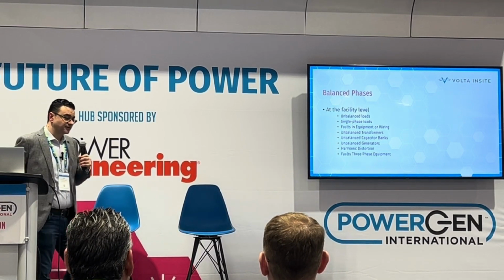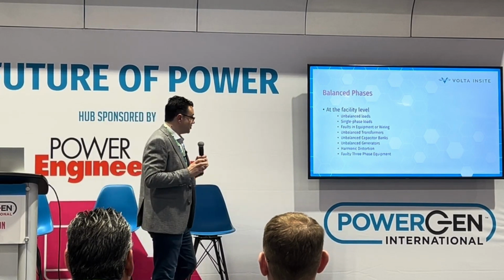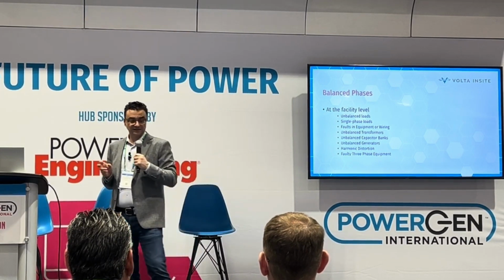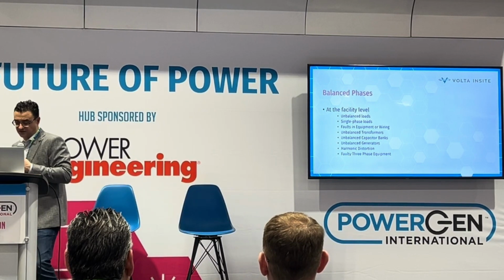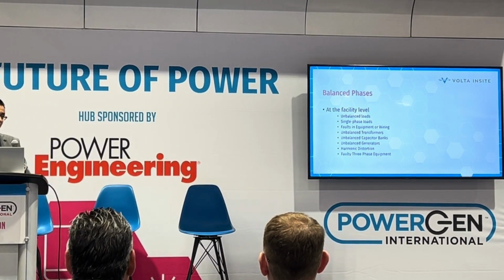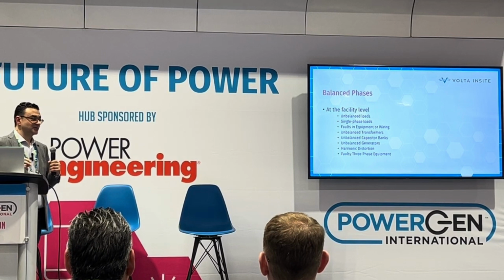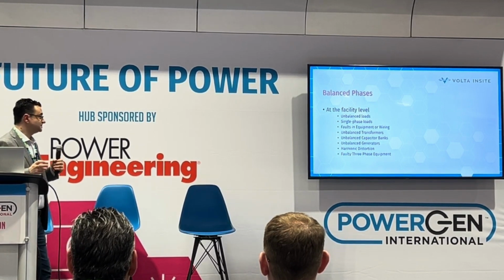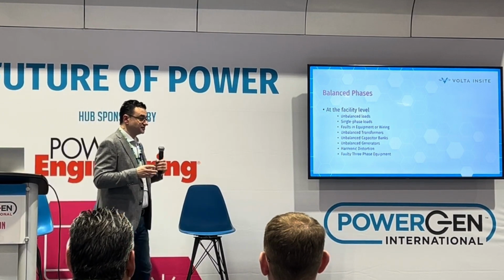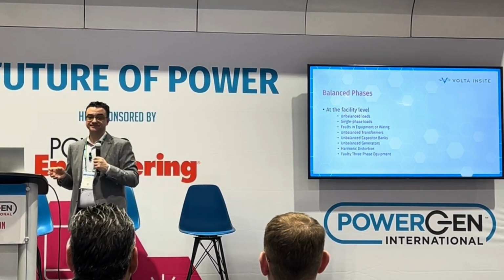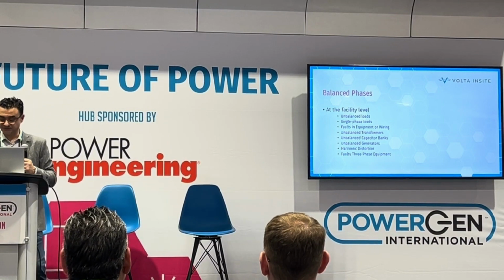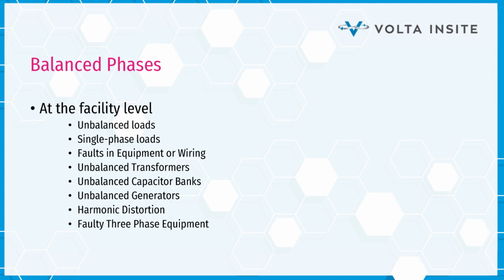And then balancing of your phases is something you have to do at the utility level. Houses, for example, will always use one phase rather than all three phases, so you have to balance out entire neighborhoods. Similarly, you need to do the same thing within a facility. You want to ensure that there are not a lot of single phase loads spread out, pulling down one side of your distribution system.